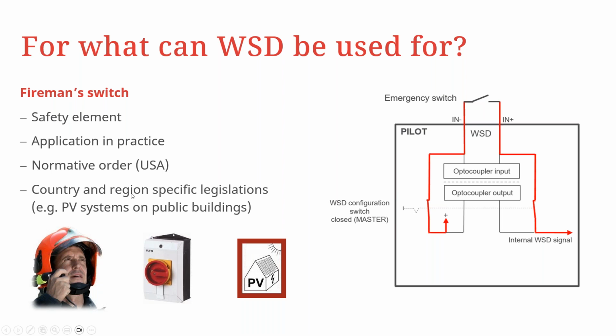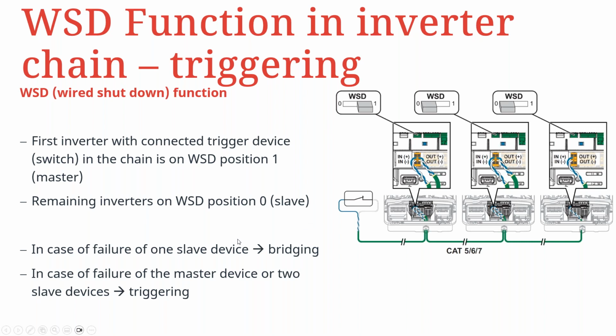And then we have other countries and regions that actually have specific legislation for PV systems on public buildings. Good. Like I mentioned earlier, if you have multiple inverters, obviously there are multiple pilots to connect. So this is how the orientation should be. The device or the pilot that is connected to the trigger switch, the WSD switch, should be in the 1 position, that is the master position, whilst the others should be in the 0 position, as you can see.